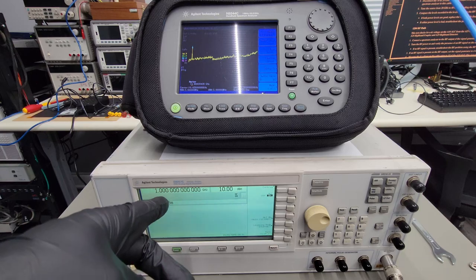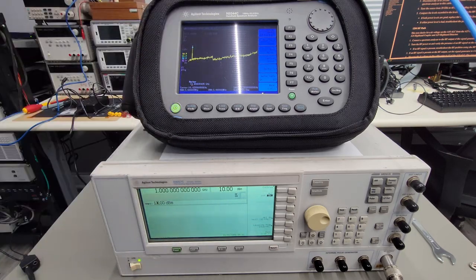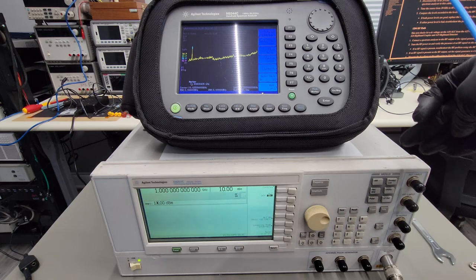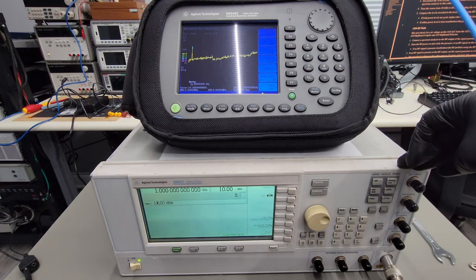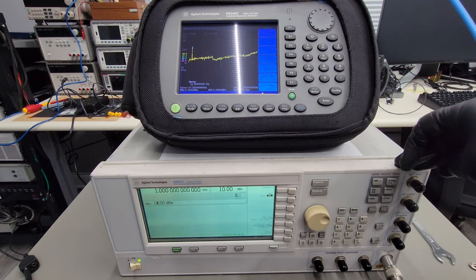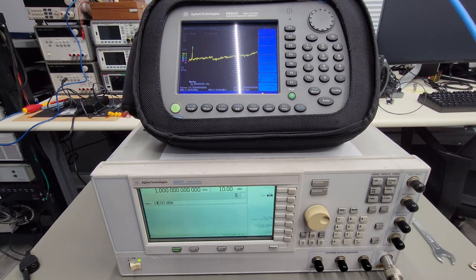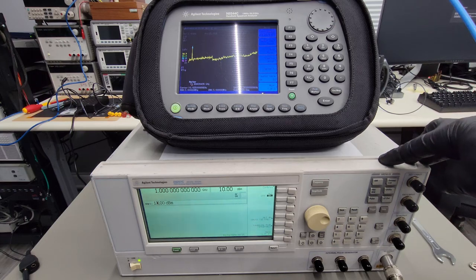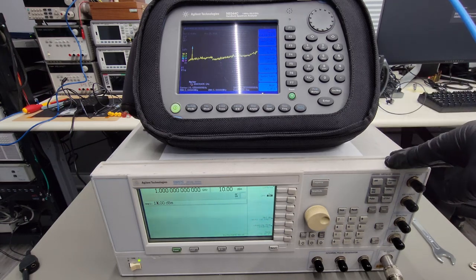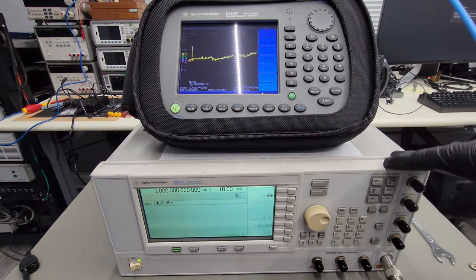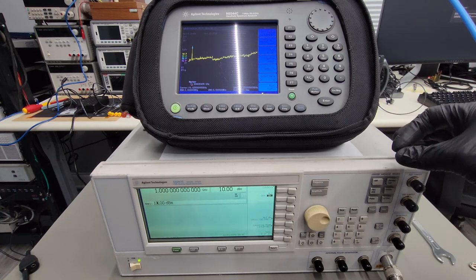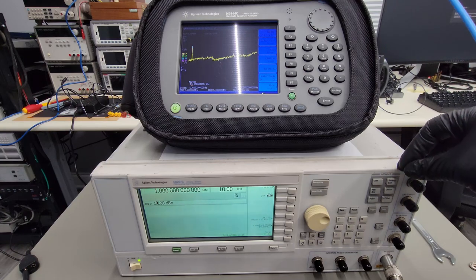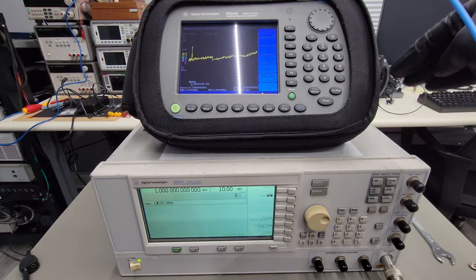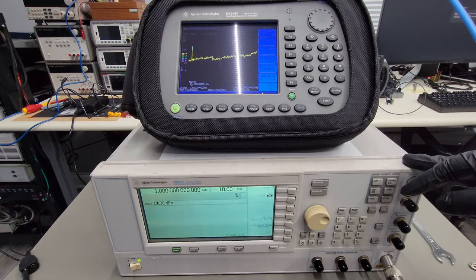I'm set to 10 dBm now on the signal gen, and on the analyzer, I'm seeing minus 20. So this could be a lot of things. It could be that RF path error we saw. This unit does have the step attenuator, and the step attenuators can also be an issue with these units, with any RF instrument, especially Agilent Keysight models. I've done more attenuators than I care to admit in these units, and they have these tiny little O-rings on each plunger that always fail. So it could be an attenuator issue. It could be related to the 1204 error that we're seeing in the self-test.